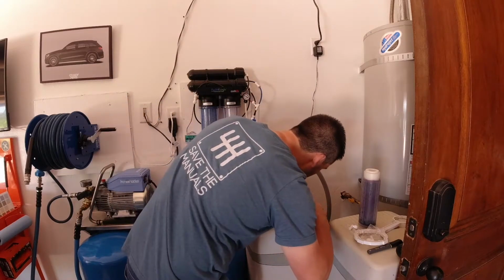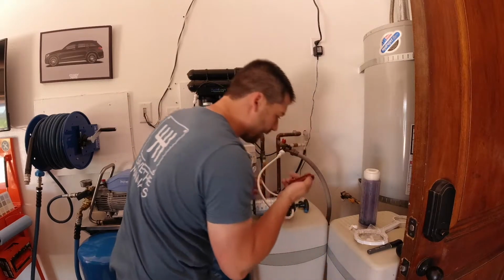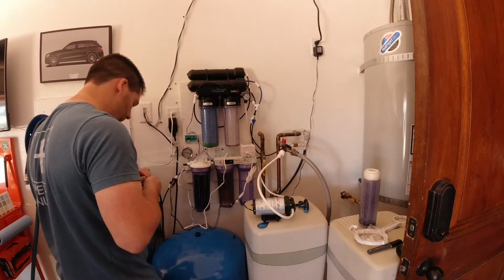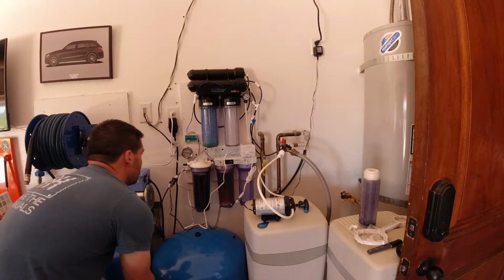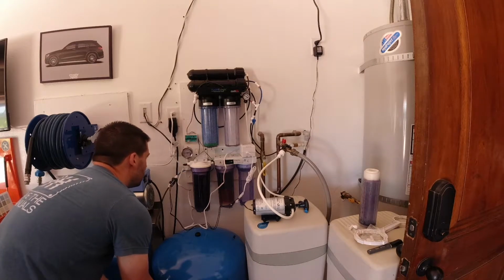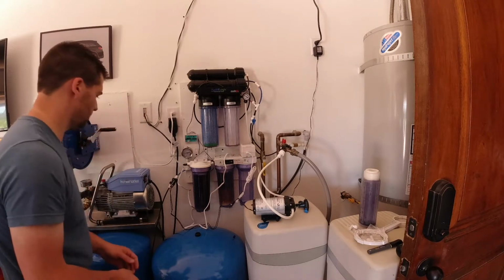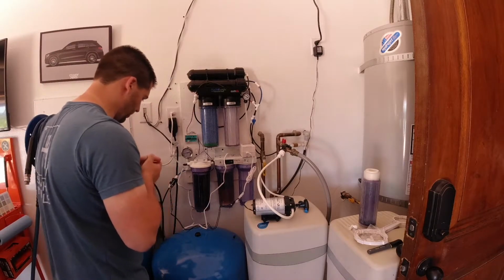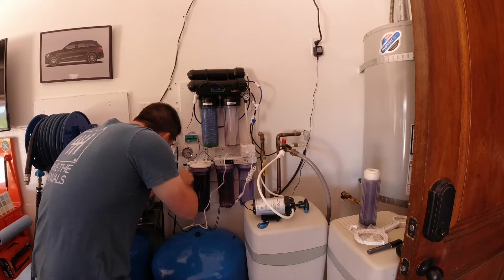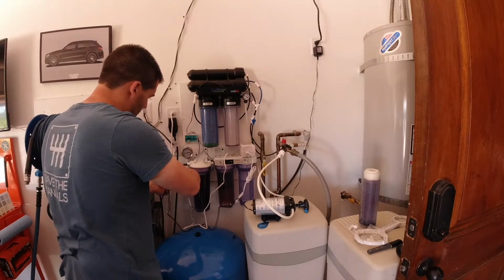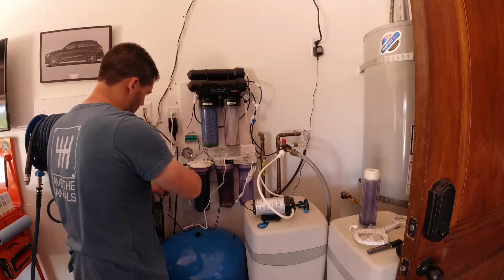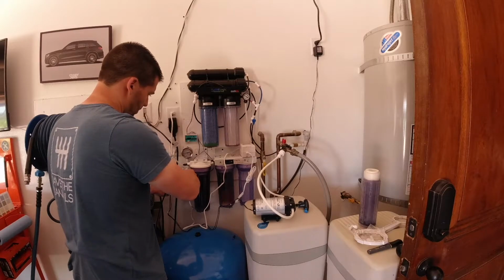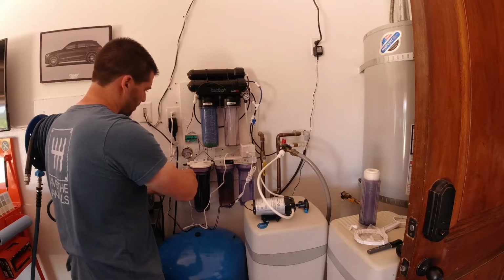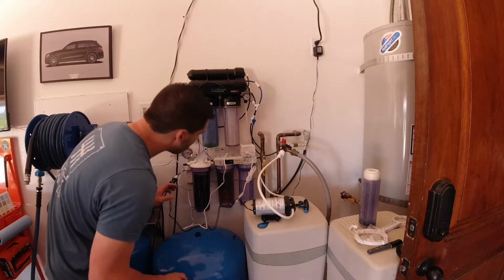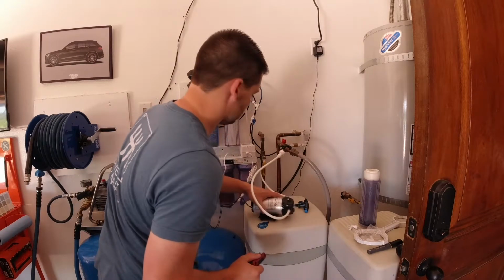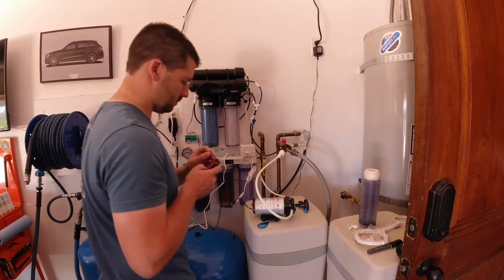Adjusting this should set my pressure on the output side. So I'm going to open up the tank and let the water flow a little to drop below the 40. That was interesting, this didn't come on. Okay, so this is pumping.